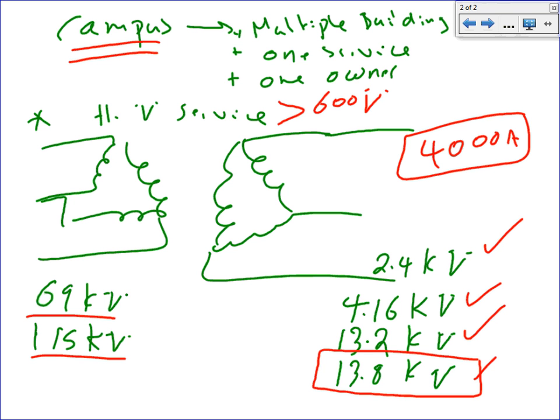Though you can get any one of these voltages. Most of the time, they give it to you guys delta delta. Why? Anybody know why delta delta? Because on the primary side, if you get that high voltage, do you really need one line to neutral? We don't. On high voltage, other than utilities, you don't connect anything line to neutral. There's no need for line to neutral.